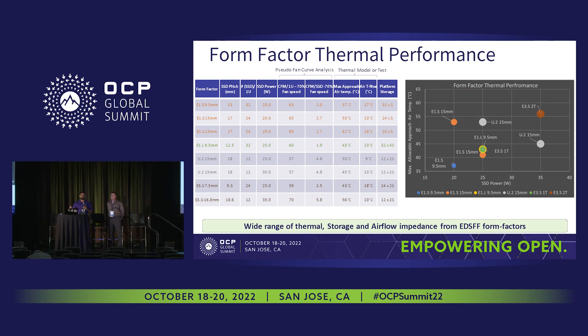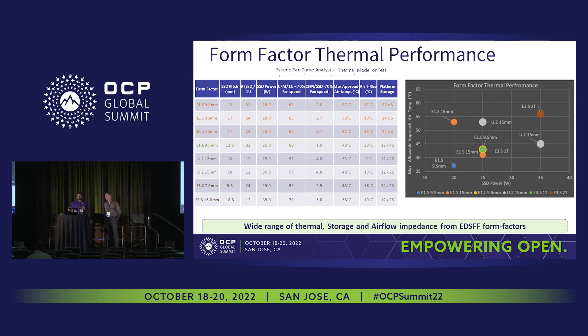For ISO fan speed comparison — which is not ISO airflow, because ISO airflow is not the right assumption — at 70% fan speed, different form factors can operate at different ambient temperatures because of their higher thermal capability and lower air impedance. The plot shows that EDSFF brings a very large range of airflow and CFM compared to U.2 or other form factors.